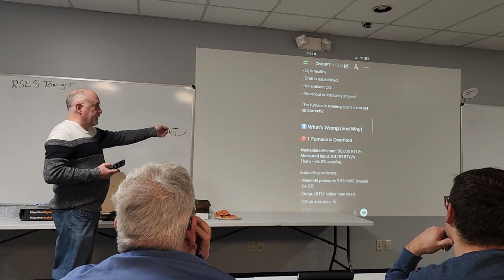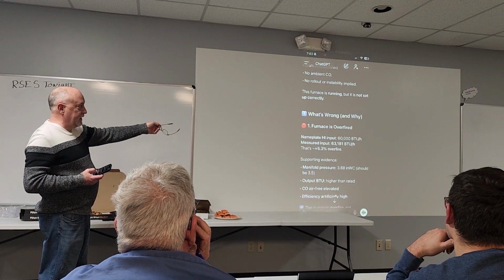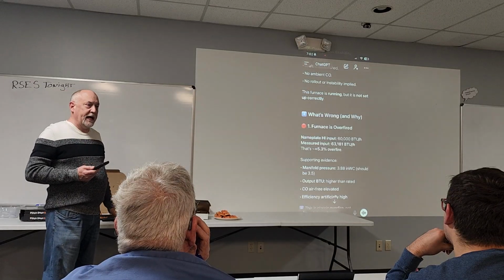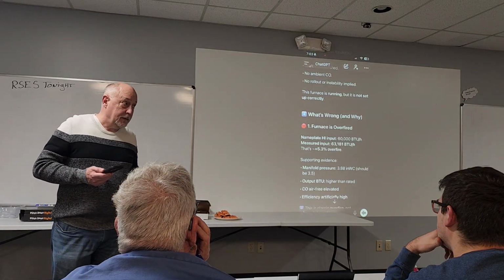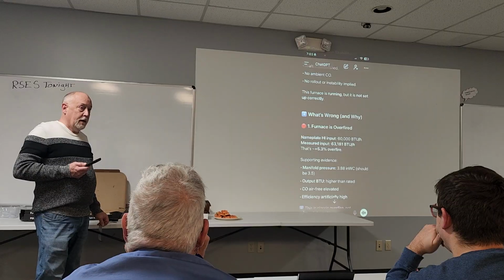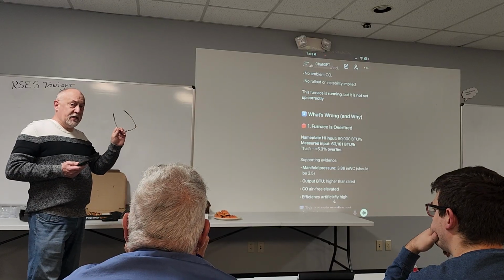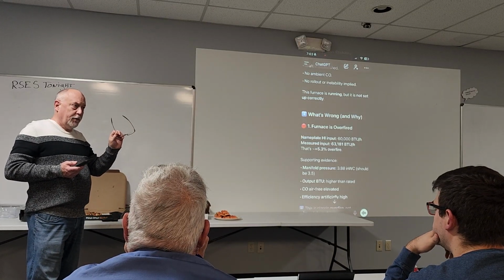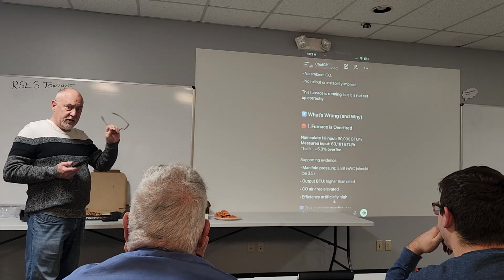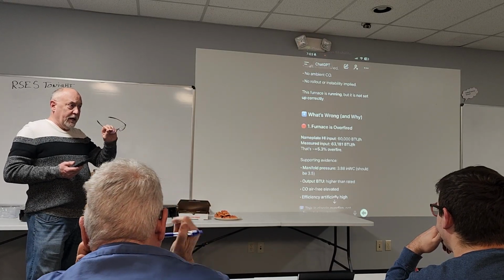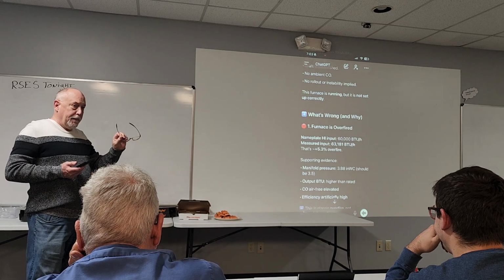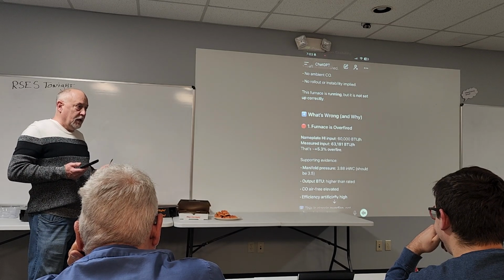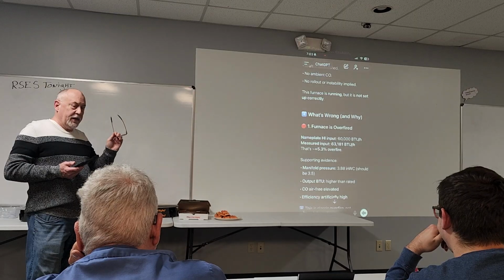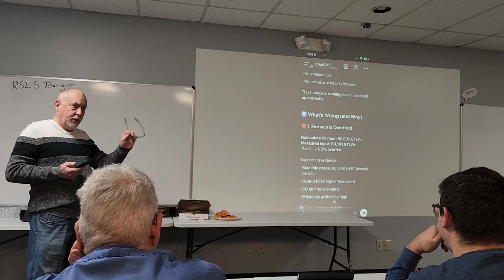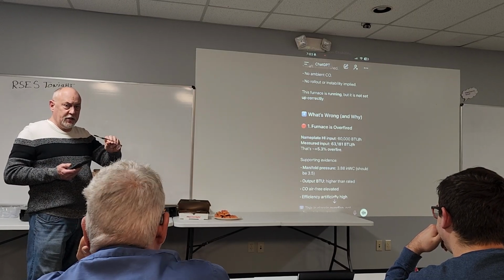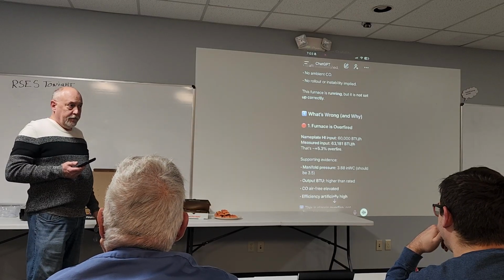What's wrong and why? The furnace is overfired. Measured input 63, that's 5% overfire. Anybody know what the maximum allowable overfire is for an appliance? Here's something important: this furnace has an allowable manifold pressure of 3.2 to 3.8 inches, so that's a pretty wide range. But the input has to be within 2%. So you could have this furnace set within the allowable manifold pressure range of 3.2 to 3.8 inches, but still be overfired.